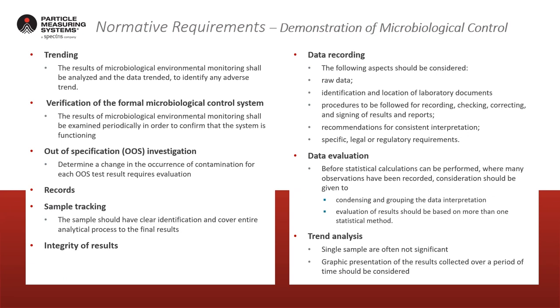The standard then looks at data trending as a key parameter and verification that the formal microbiological control system is actually working, including review for out-of-spec investigations. All records must demonstrate compliance with clear sample tracking that covers the entire route from sample collection through to the final result and the integrity of those results. Data recording should follow expectations for recording and evaluating data using various statistical techniques, including grouping and condensing data to come up with a more holistic answer.